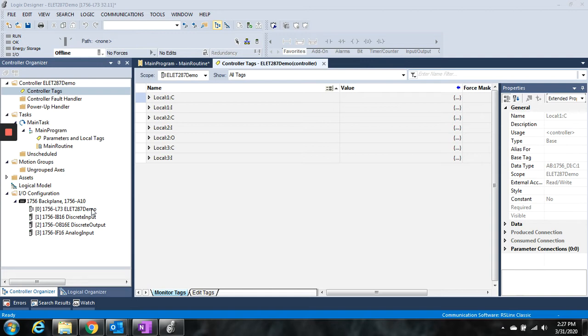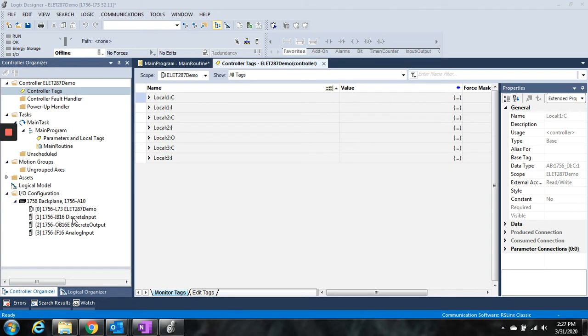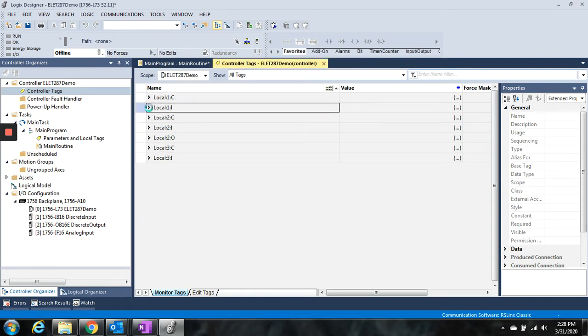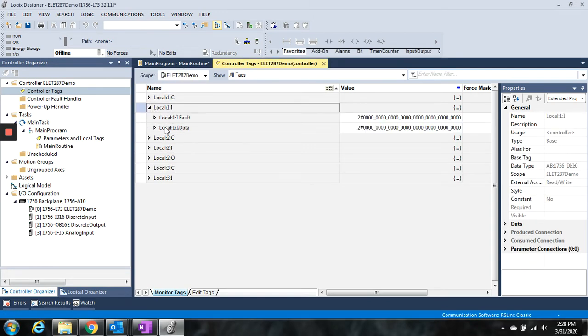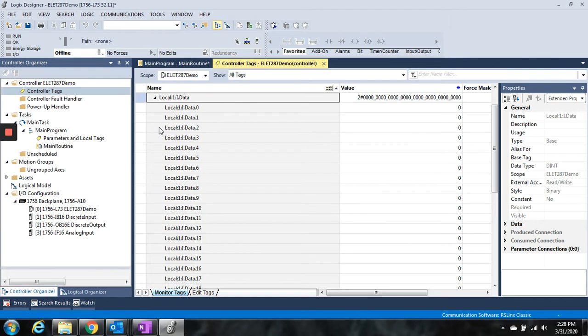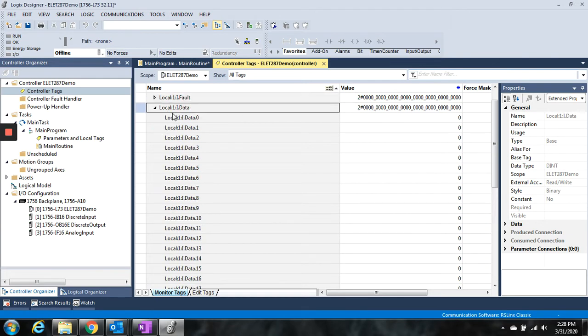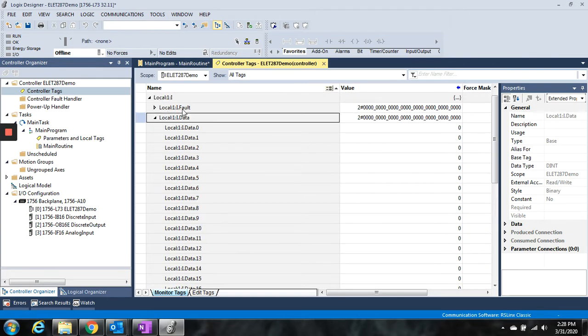So that's how I go about configuring this chassis. I put the cards in their slots, and then now we can come and look at the addressing for those slots here in the controller tags. So the input card in slot 1 would get mapped to local 1 colon I, right here. And when you expand it out, you'll see we have fault data and data.